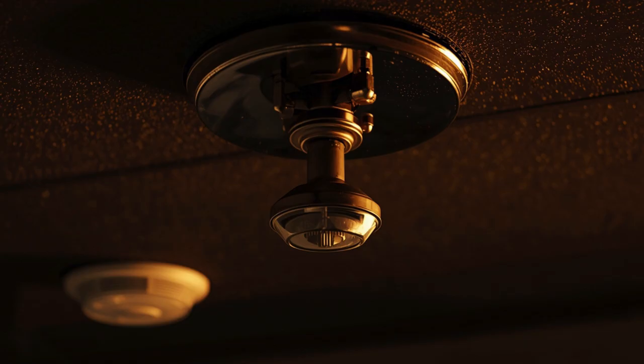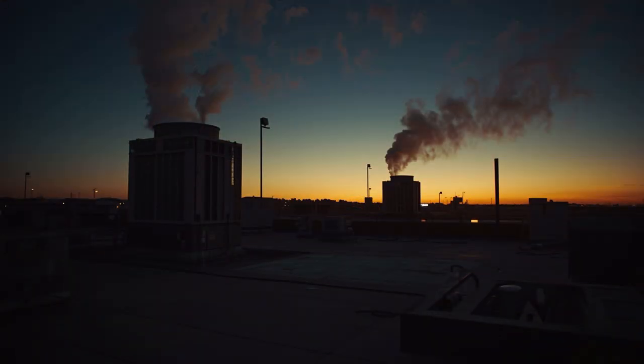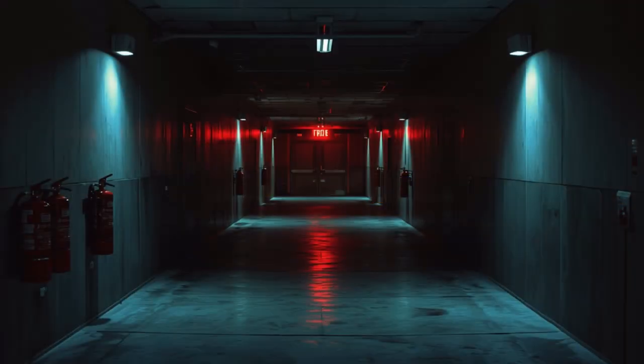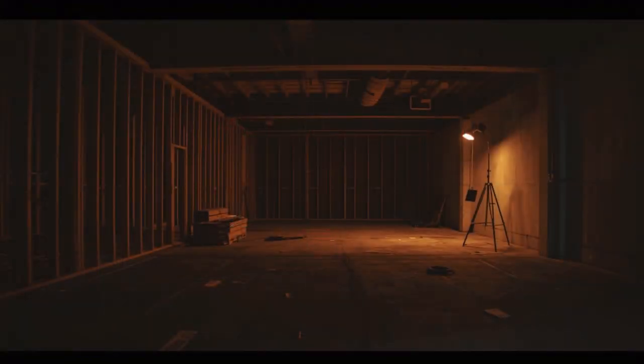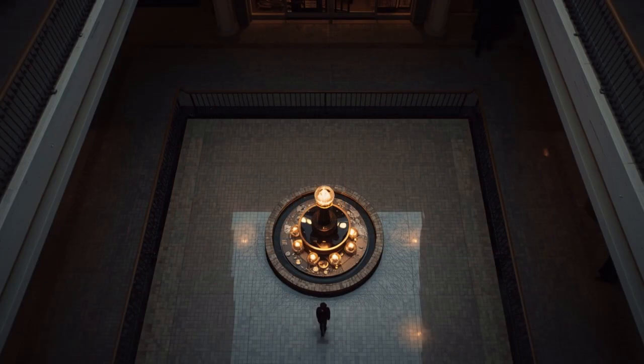The fire safety systems, too, were more deeply integrated into the overall building design than their purely protective function might suggest. The smoke control strategy for the atrium, the decision to manage smoke by maintaining a clear layer at low level while exhausting smoke from the upper reservoir, was a fire safety decision driven by the physics of smoke movement and the goal of protecting evacuating occupants. But it was also a spatial decision, because the strategy only worked in a space with sufficient height above the occupied zone to accommodate the smoke reservoir without immediately threatening the people below.